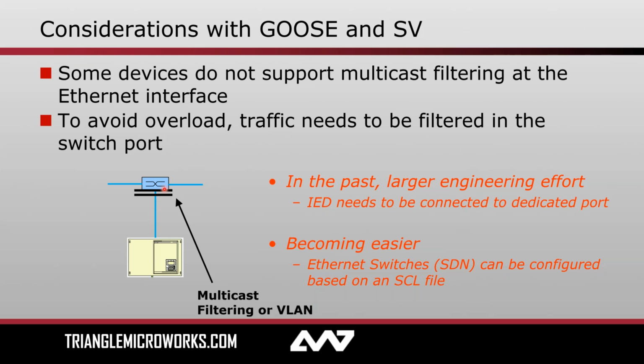Basically, a lot of the information needed to intelligently configure the switch is already contained in the SCD file. So there are several vendors out there that are taking that SCD file, reading out maybe the network topology, knowing which devices are connected where, and able to semi-automatically configure these switches to really reduce the burden on the substation engineers, potentially network engineers, whoever's doing that switch configuration.